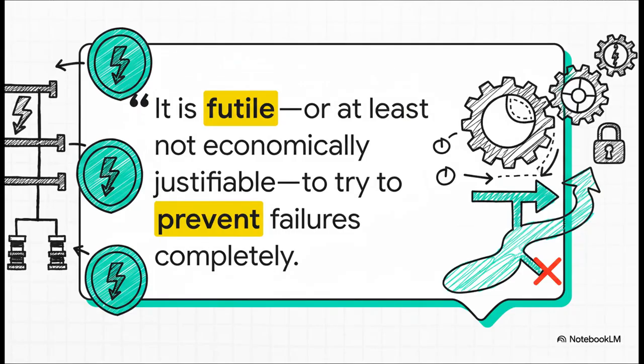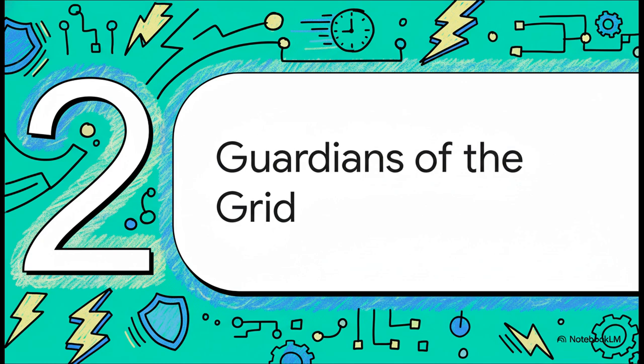Now here's what's really interesting. The whole philosophy behind protecting the grid: the goal isn't to build a system that can never ever fail. I mean, that would be impossible, not to mention insanely expensive. Instead, as this quote from our source material explains, the real goal is to accept that, hey, failures will happen. The profitable and smart thing to do is build a system that can intelligently deal with the effects and limit the damage. And that, right there, brings us to the heroes of our story. The systems that aren't designed to prevent the failure, but to contain it in the blink of an eye. These are the guardians of the grid, protective relays.